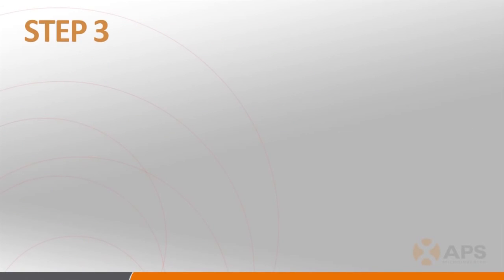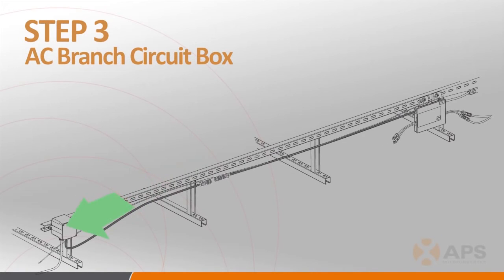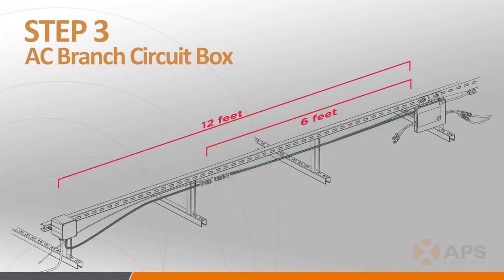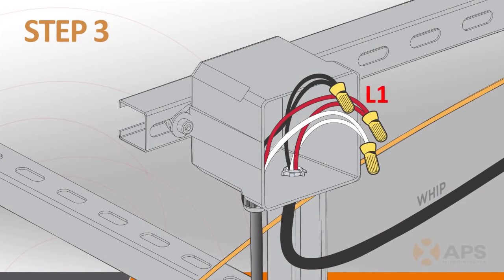Step 3 involves installing the AC branch circuit junction box in a suitable location, as close to the end of a branch of modules as possible. You'll have approximately 12 feet of AC cable to work with — 6 feet of cable associated with the last inverter in the branch, and 6 feet of AC connector cable, sometimes called a whip. Make sure to wire the conductors correctly: L1 is red, L2 is black, and neutral is white.